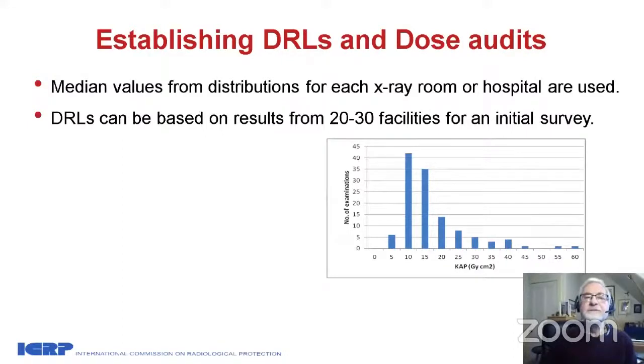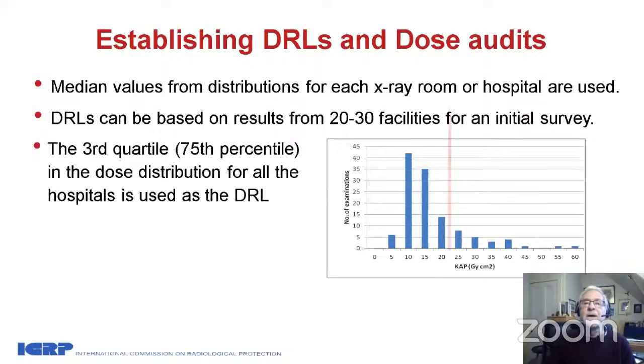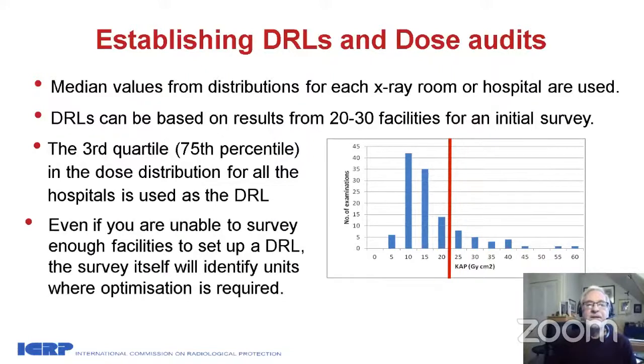So median values from the distribution for each X-ray room or hospital. We then look at this distribution. Typically 20 or 30 facilities may be sufficient for an initial survey. We take the 75th percentile in the dose distribution for all the hospitals and use that as the DRL. And even if you're unable to survey enough facilities to set a DRL in this way, it will still identify those facilities where doses are higher.